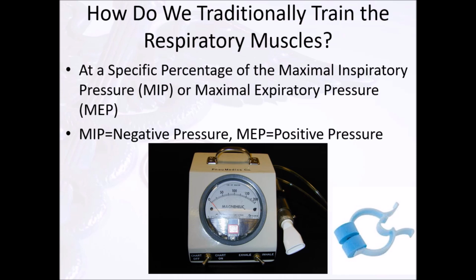And in fact, we can use this same device. The person puts this in their mouth, they wear the nose clip, and they could do inspiratory efforts up to 50 centimeters of water, and that could be their inspiratory muscle training period for how many breaths we'd like them to use. The same would be true for expiratory training. We would obtain a positive pressure, a maximal expiratory pressure. We'd move this particular dial to exhale. We'd have the person wear the nose clip, put this mouthpiece in their mouth, take a full deep breath and exhale into the mouthpiece with hopefully a good seal. And we would probably find a maximal expiratory pressure of about 150 centimeters of water.